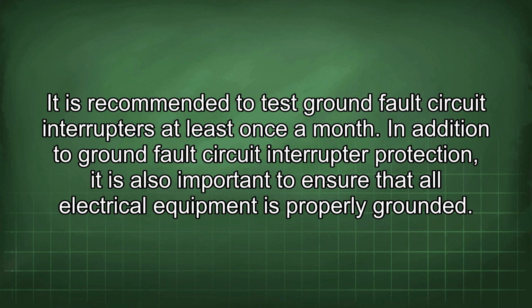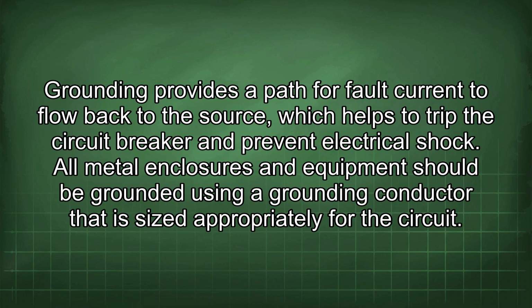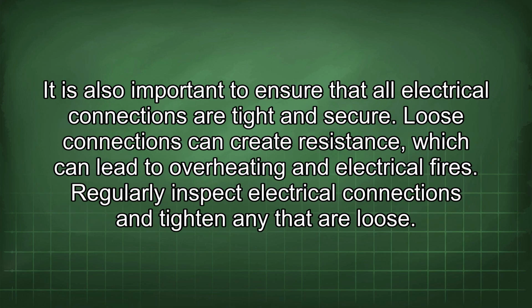In addition to ground fault circuit interrupter protection, it is also important to ensure that all electrical equipment is properly grounded. Grounding provides a path for fault current to flow back to the source, which helps to trip the circuit breaker and prevent electrical shock. All metal enclosures and equipment should be grounded using a grounding conductor that is sized appropriately for the circuit. It is also important to ensure that all electrical connections are tight and secure. Loose connections can create resistance, which can lead to overheating and electrical fires. Regularly inspect electrical connections and tighten any that are loose.